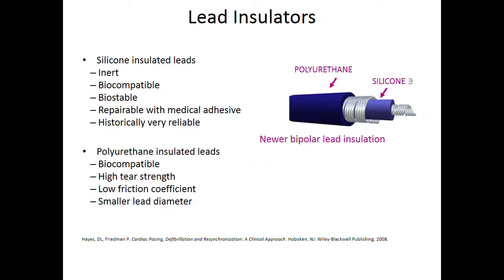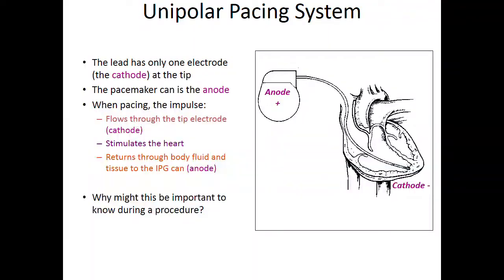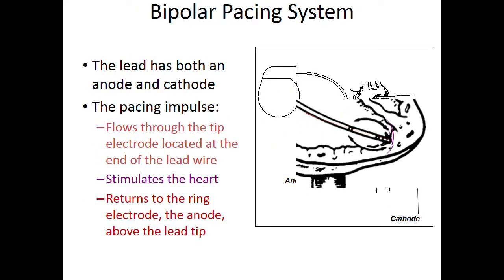The older style pacemakers years ago would actually sense the heart by recording electrical potentials between here and the actual can of the pacemaker. So that's why in an older pacemaker years ago, a microwave oven, for example, could interfere with it, because the antenna for the sensing of the pacemaker was very wide, all the way from where the wire goes in to where the battery pack is. But in later years, and that's just a representation, we now use what's called a bipolar lead, which means that the two little electrodes are totally within the heart. So they're much less susceptible to interference from appliances and generators and things like that.